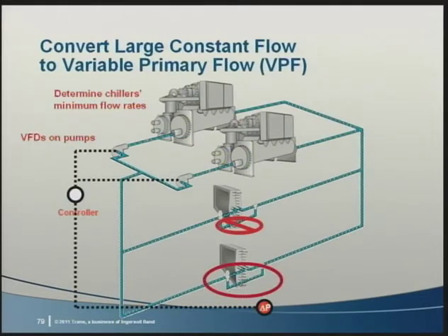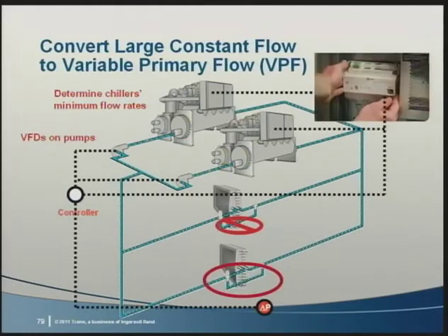But we now need a system controller to sequence chillers on and off, as well as to ramp the pumps up and down as the chillers sequence. When the system is larger, the opportunity for savings is also larger, but so is the investment, both in terms of work and cost. So, what has to happen to convert a system from primary-secondary to variable primary flow?